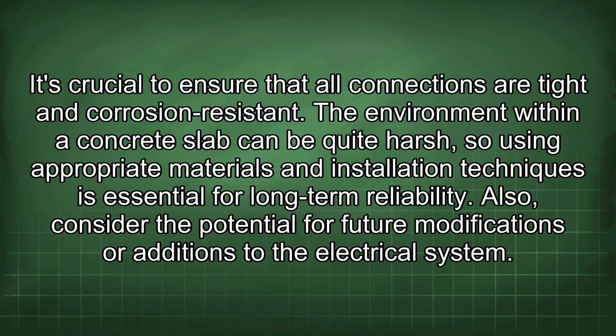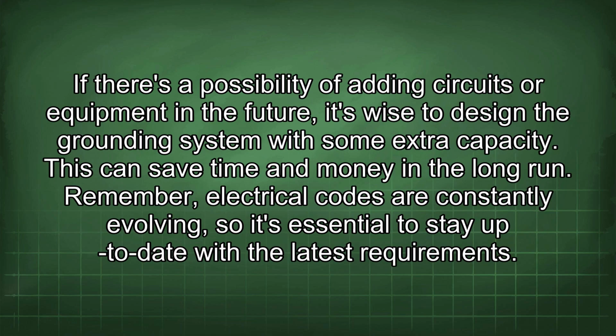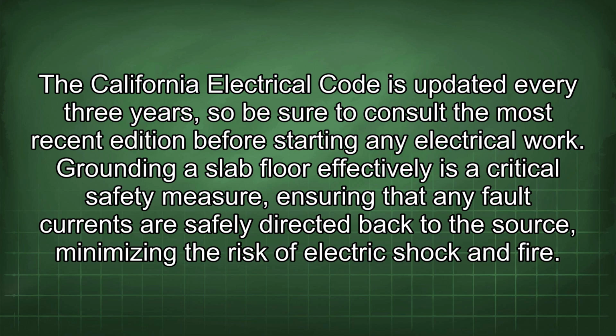Also, consider the potential for future modifications or additions to the electrical system. If there's a possibility of adding circuits or equipment in the future, it's wise to design the grounding system with some extra capacity. This can save time and money in the long run. Remember, electrical codes are constantly evolving, so it's essential to stay up to date with the latest requirements. The California Electrical Code is updated every 3 years, so be sure to consult the most recent edition before starting any electrical work. Grounding a slab floor effectively is a critical safety measure, ensuring that any fault currents are safely directed back to the source, minimizing the risk of electric shock and fire.